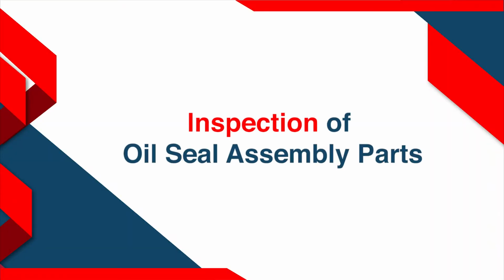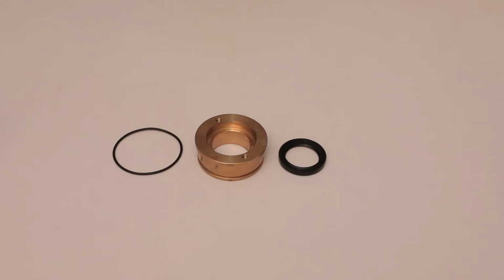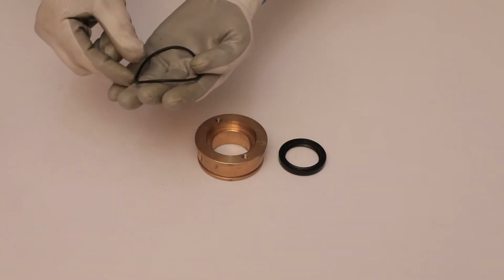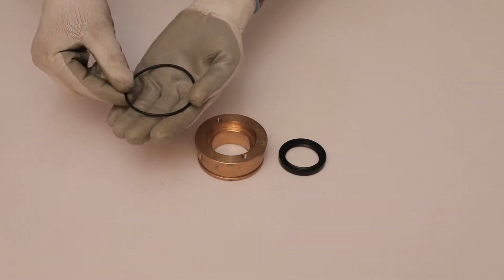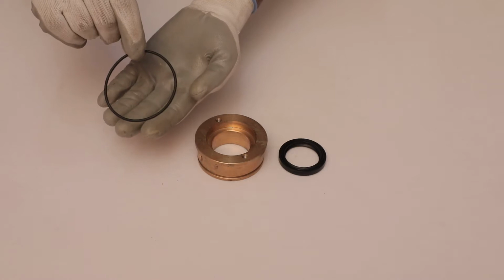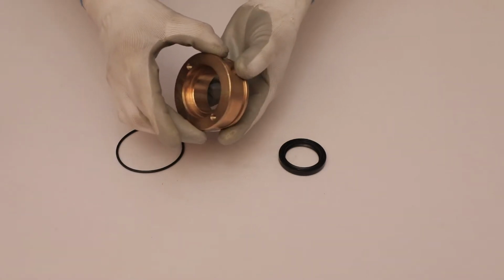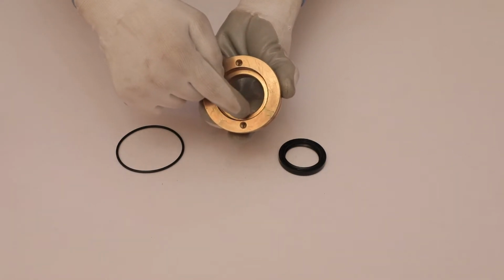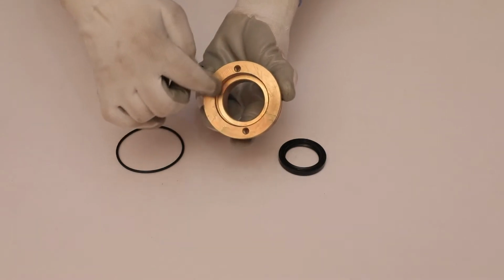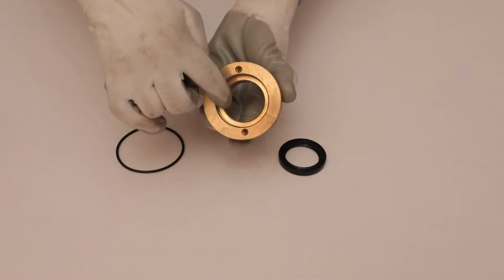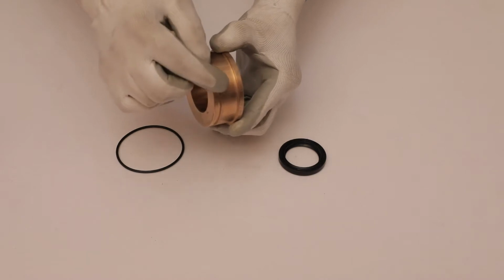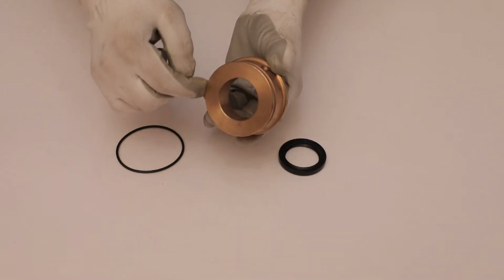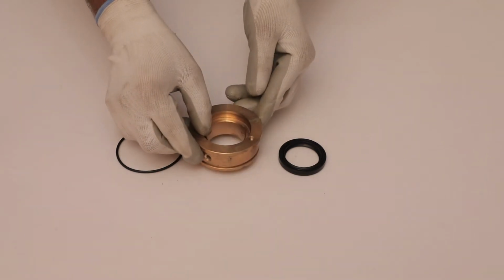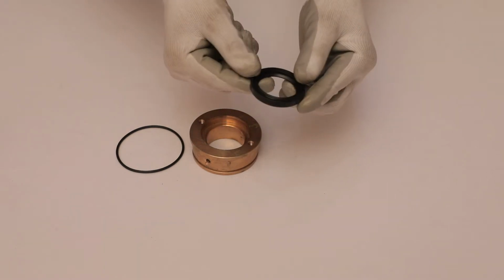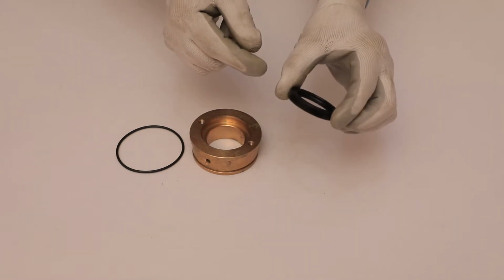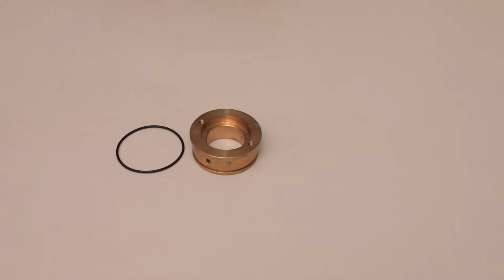Inspection of oil seal assembly parts. Check O-ring for looseness and thickness. Inspect the surface of oil seal, periphery and groove of oil seal cover for any damage. It is a standard practice that once oil seal is removed, replace it with a new one.